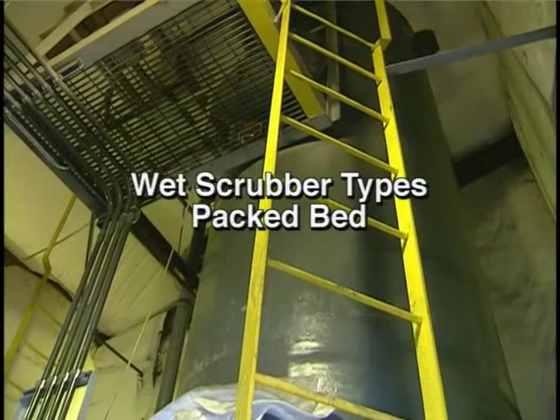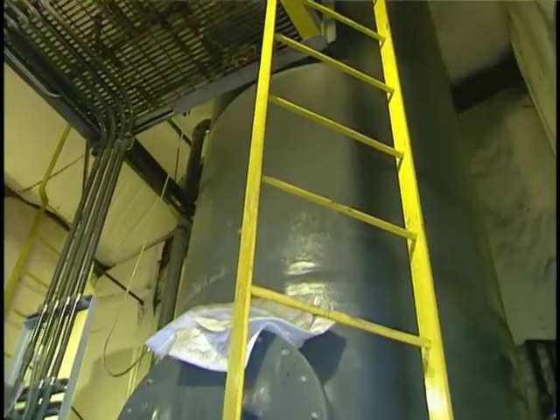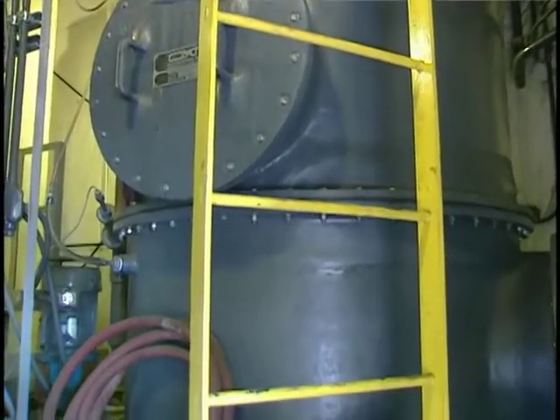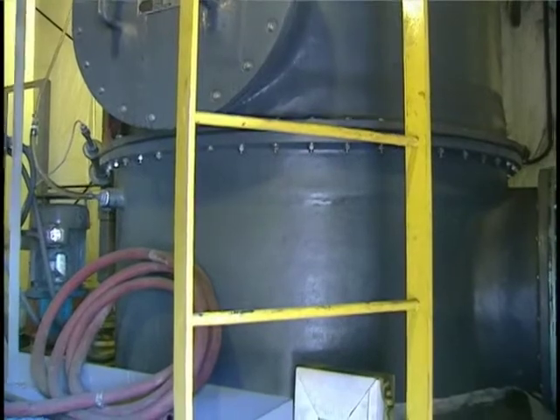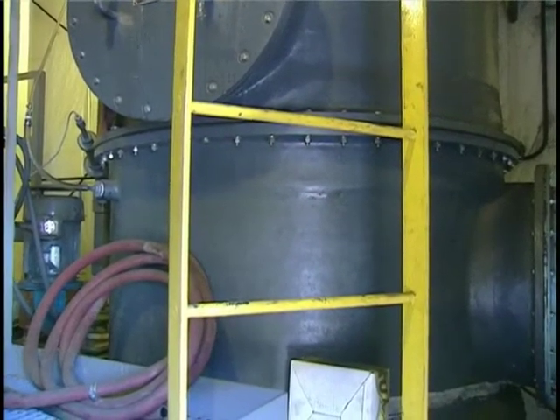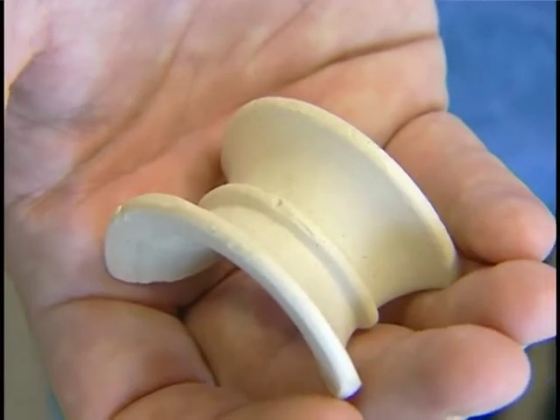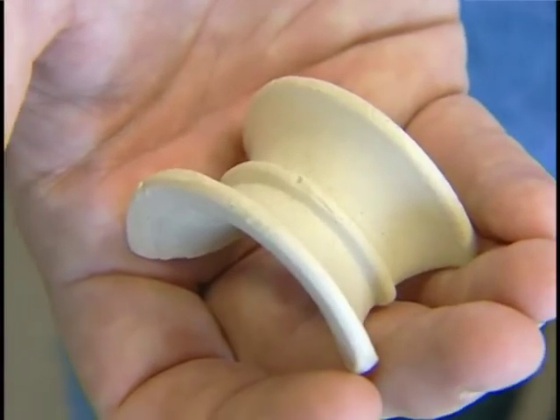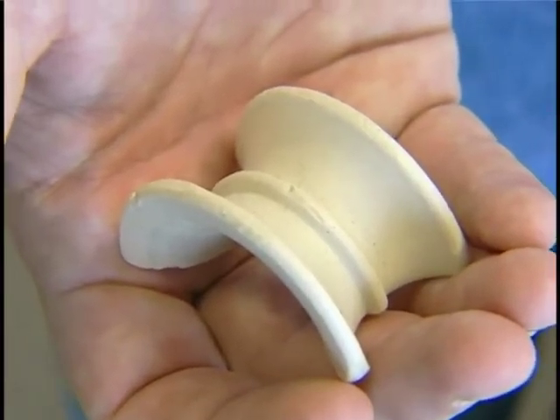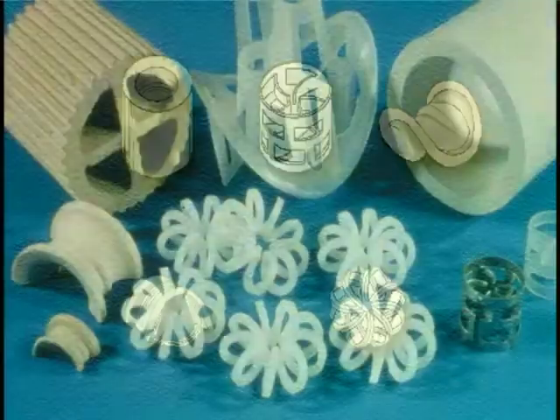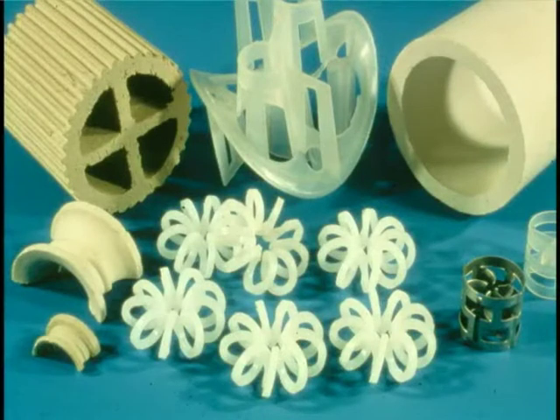Packed bed scrubbers are another type of medium energy collector. Packed bed collectors spread the liquid over packing material in order to provide a large surface area for particle impaction. There are many designs for the packing materials, but they all have large surface area while maintaining open areas for the gas flow. Although they are usually made of plastic, metal and ceramic packings are available when plastic cannot be used.